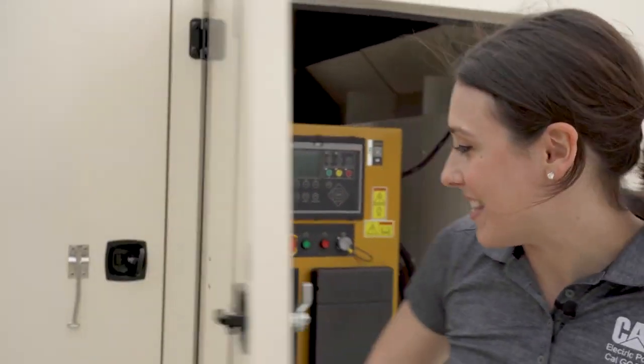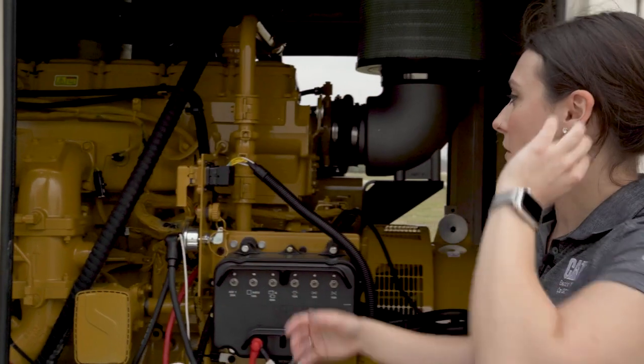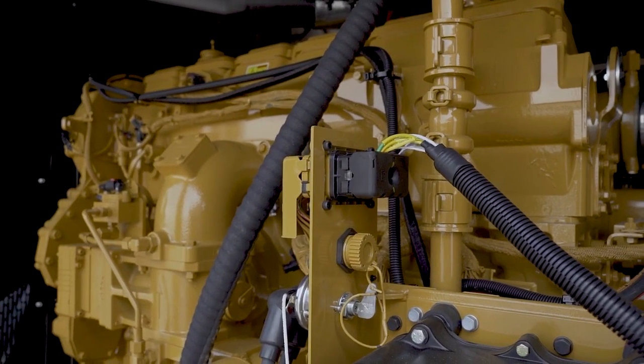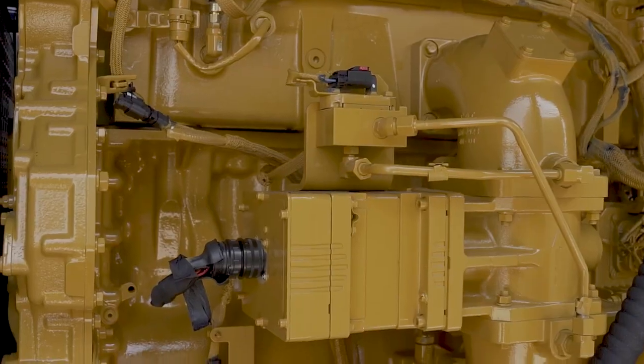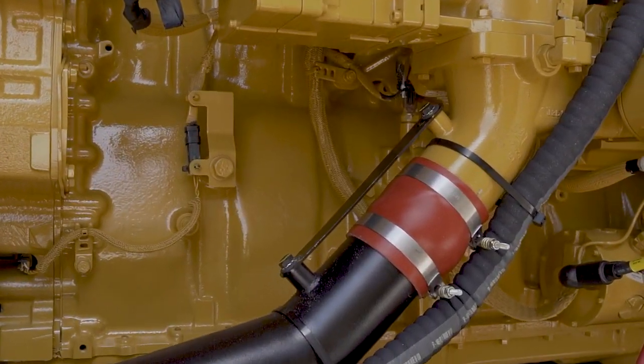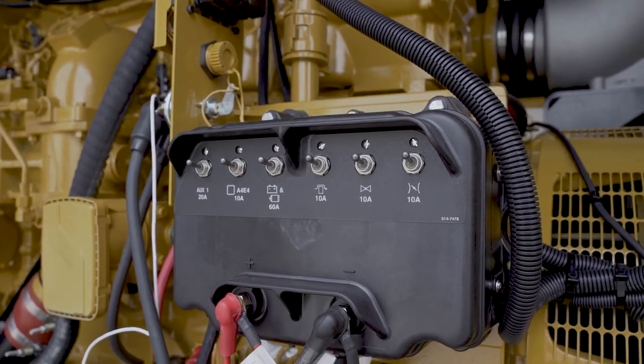Over here we'll look at our radiator and CG18 engine. The CG18 is an 18-liter lean burn engine. This lean burn design allows for lower exhaust temperature, lower NOx and CO emissions, better fuel efficiency, and better power density for the unit. The reduced emissions allow the unit to be run for both standby and demand response applications, as it is certified for both emergency and non-emergency usage.